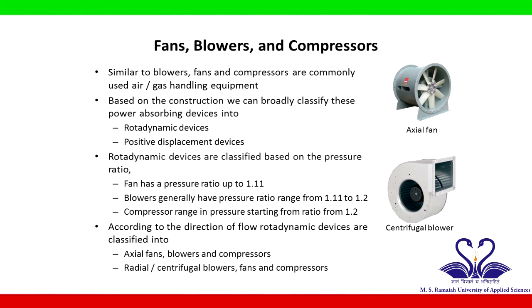Fan has a pressure ratio up to 1.11. Blowers generally have pressure ratio range from 1.11 to 1.2. Compressors range in pressure ratio starting from 1.2.